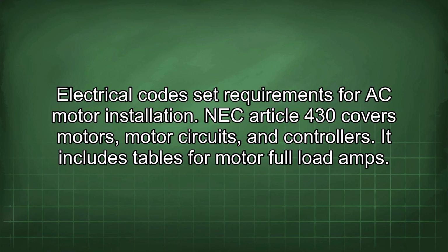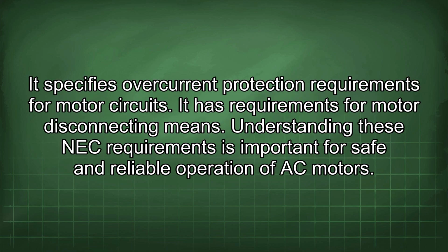Electrical codes set requirements for AC motor installation. NEC Article 430 covers motors, motor circuits, and controllers. It includes tables for motor full load amps. It specifies overcurrent protection requirements for motor circuits. It has requirements for motor disconnecting means. Understanding these NEC requirements is important for safe and reliable operation of AC motors.